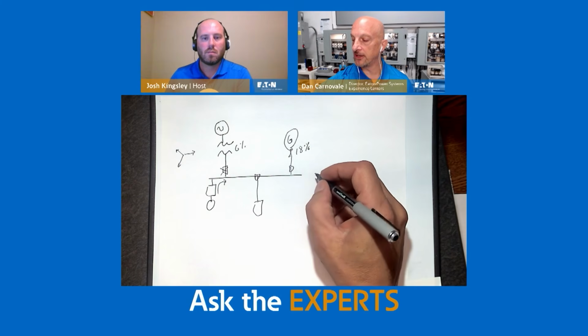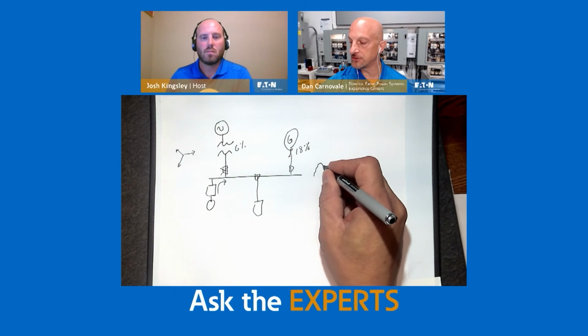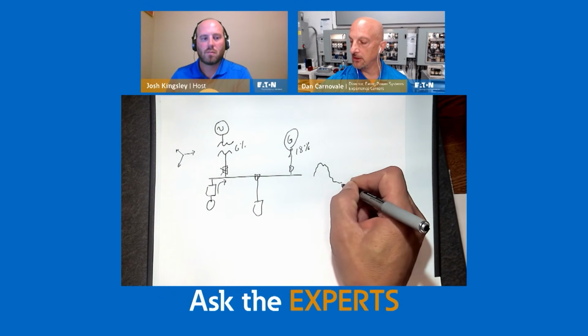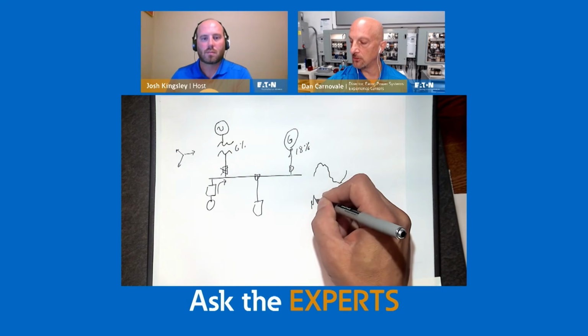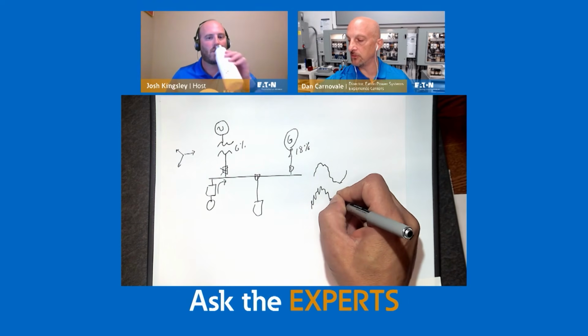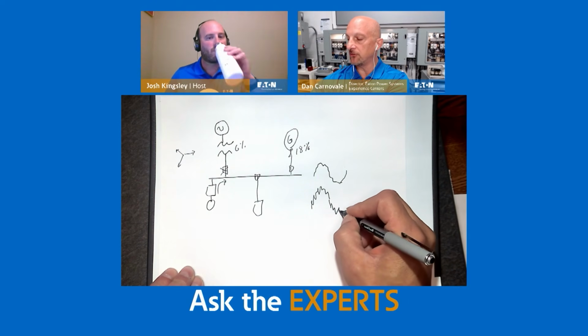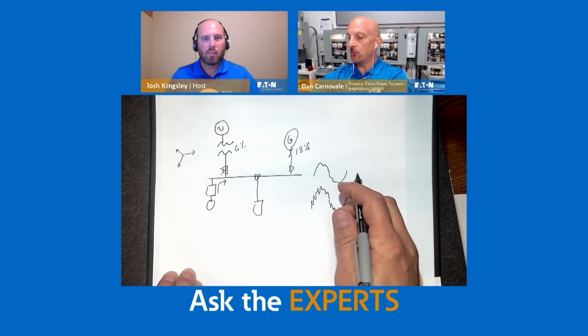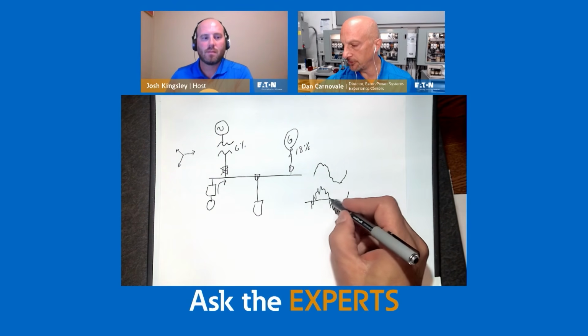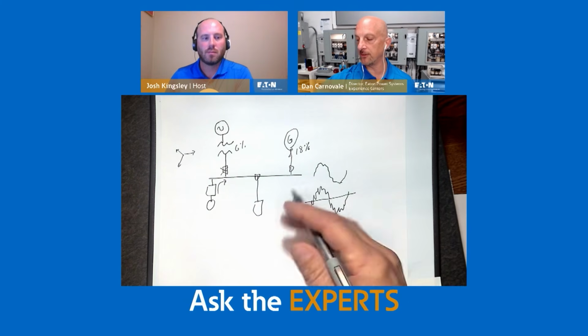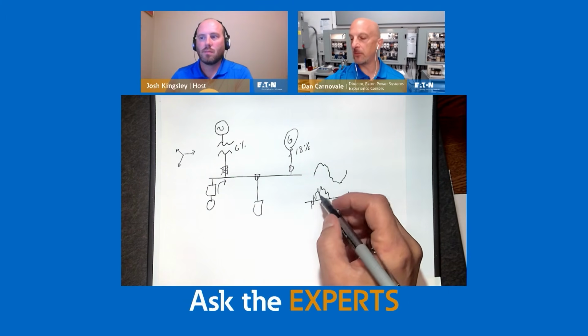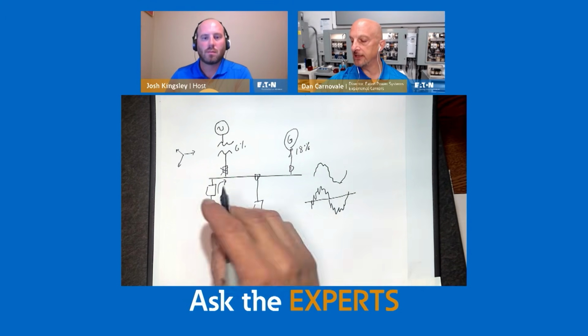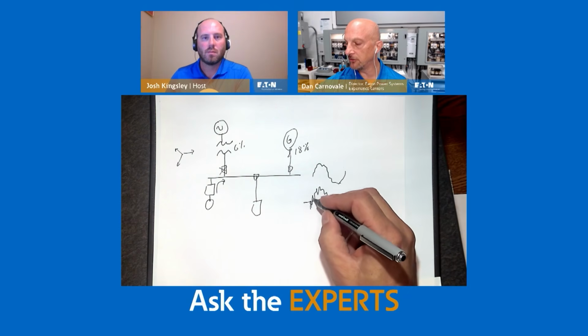Sometimes we'll have problems. And like I said, maybe we go from a voltage distortion that looks somewhat bad to something that looks horrible. And when I say horrible, I mean, it could get really ugly pretty fast. Because again, you've got 3 times the impedance. And what's that going to cause? You might actually have what we call multiple zero crossings. I'll explain a couple of scenarios with that, but you could have a bad voltage distortion. So by cleaning up the harmonics here, this goes back to normal.